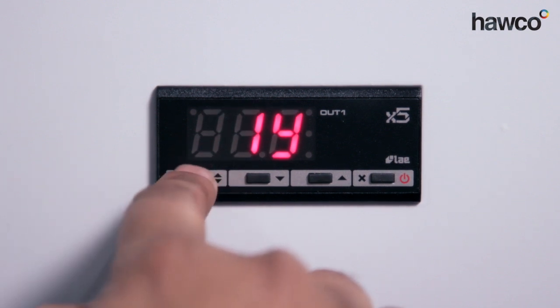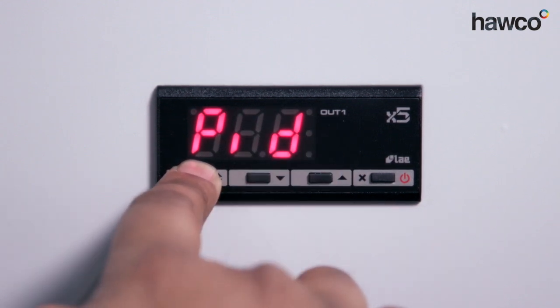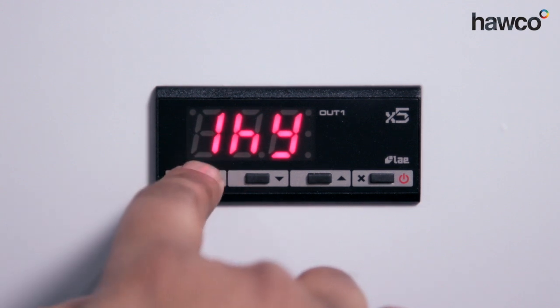Now this one is 1HY. It's basically choosing whether we're going to go for a hysteresis, a differential, or proportional bandwidth. I always prefer hysteresis over proportional bandwidth because the bandwidth can be very complicated to set up. Hysteresis is nice and simple — it will go on a differential of degrees as per what we're going to set up now.